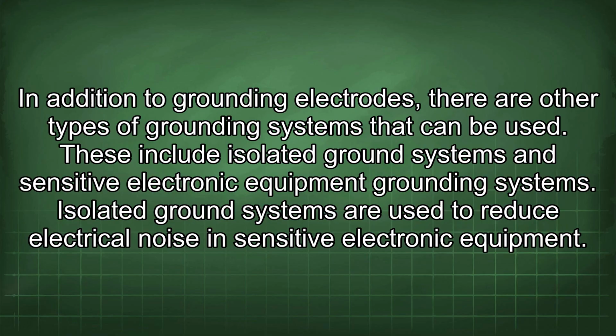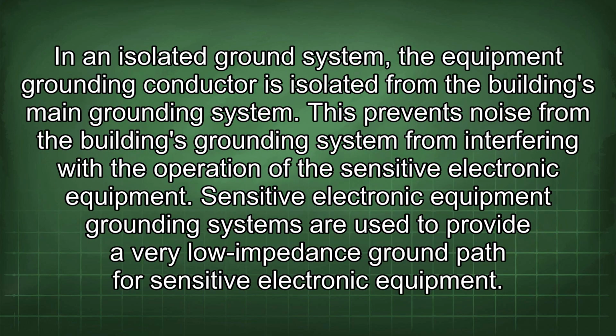In addition to grounding electrodes, there are other types of grounding systems that can be used. These include isolated ground systems and sensitive electronic equipment grounding systems. Isolated ground systems are used to reduce electrical noise in sensitive electronic equipment. In an isolated ground system, the equipment grounding conductor is isolated from the building's main grounding system. This prevents noise from the building's grounding system from interfering with the operation of the sensitive electronic equipment.